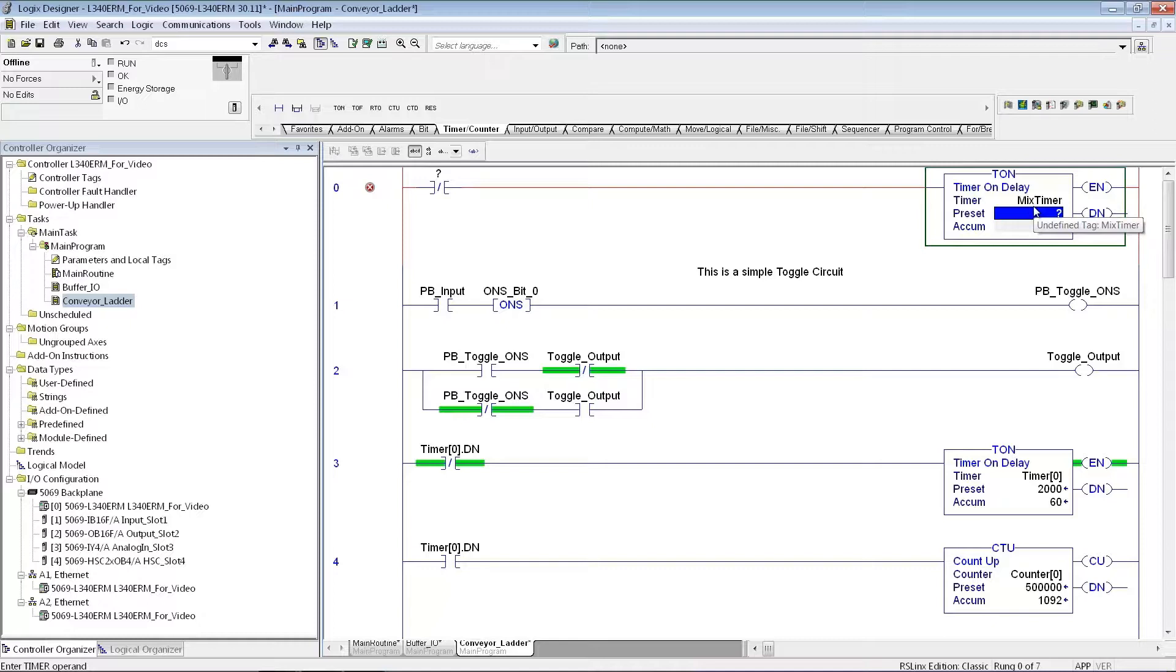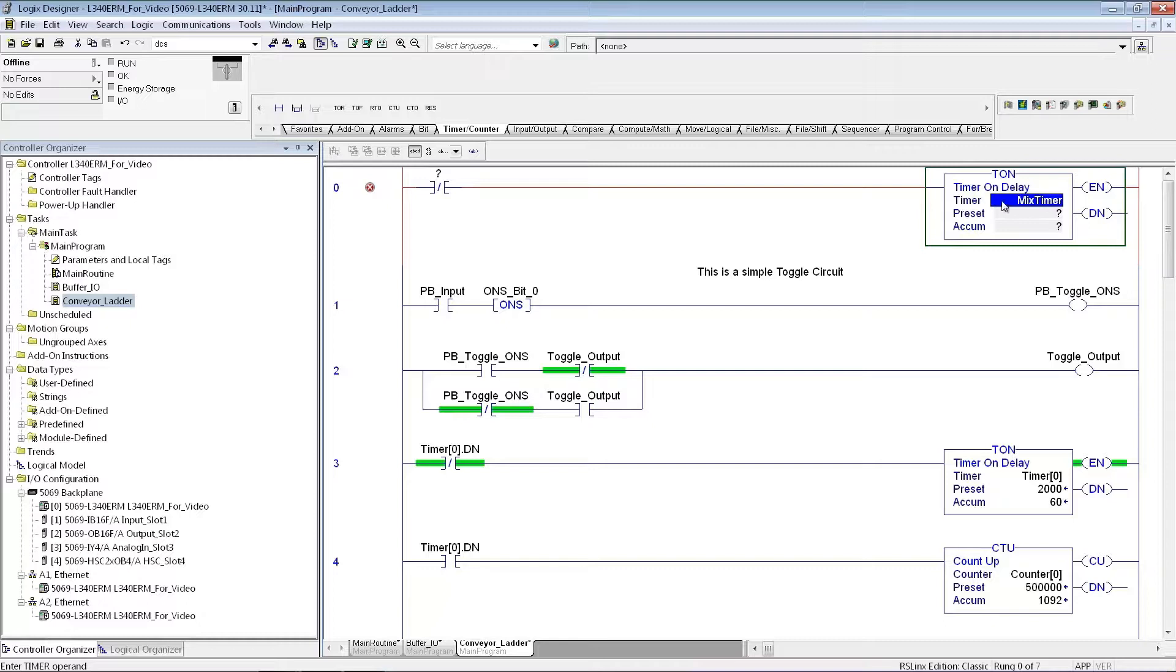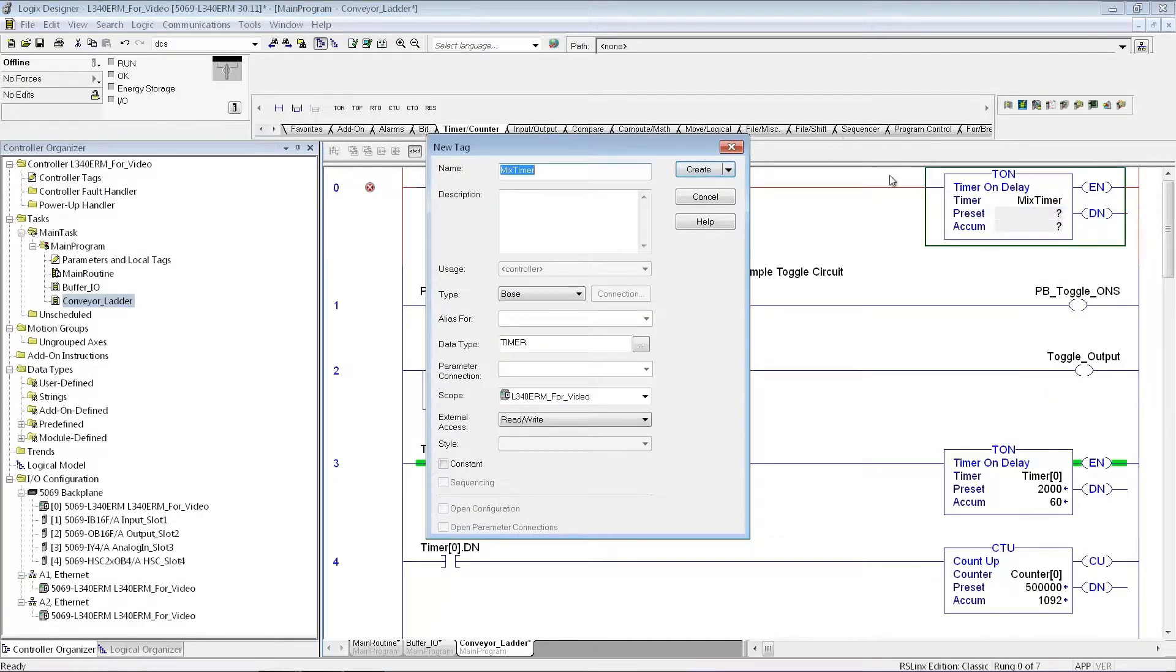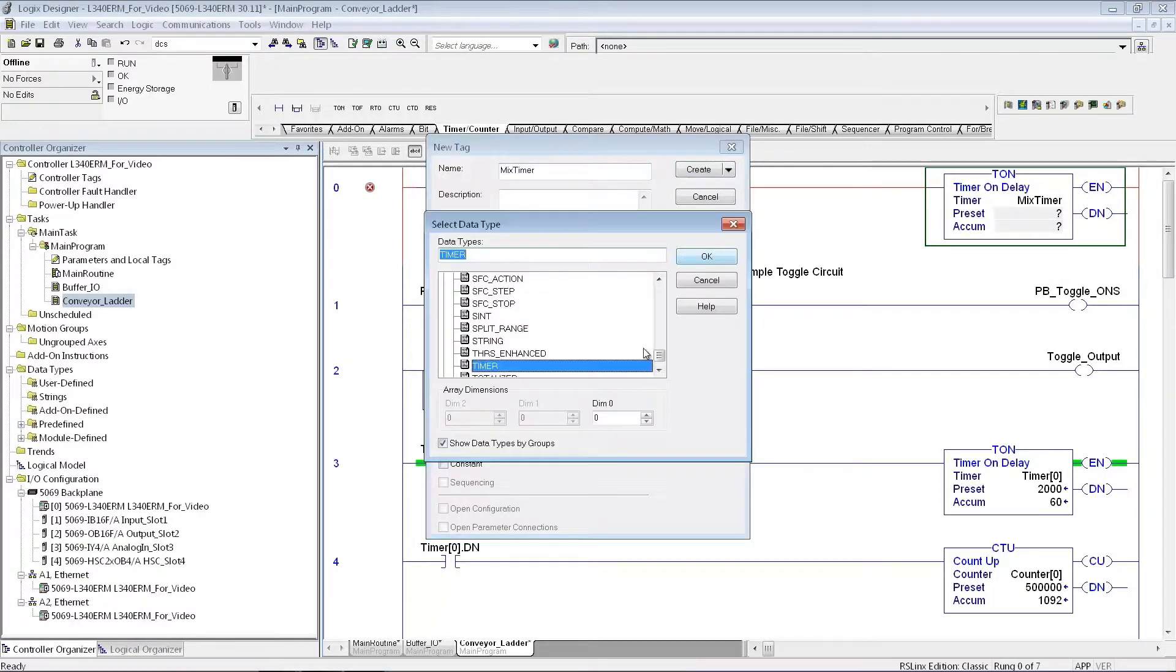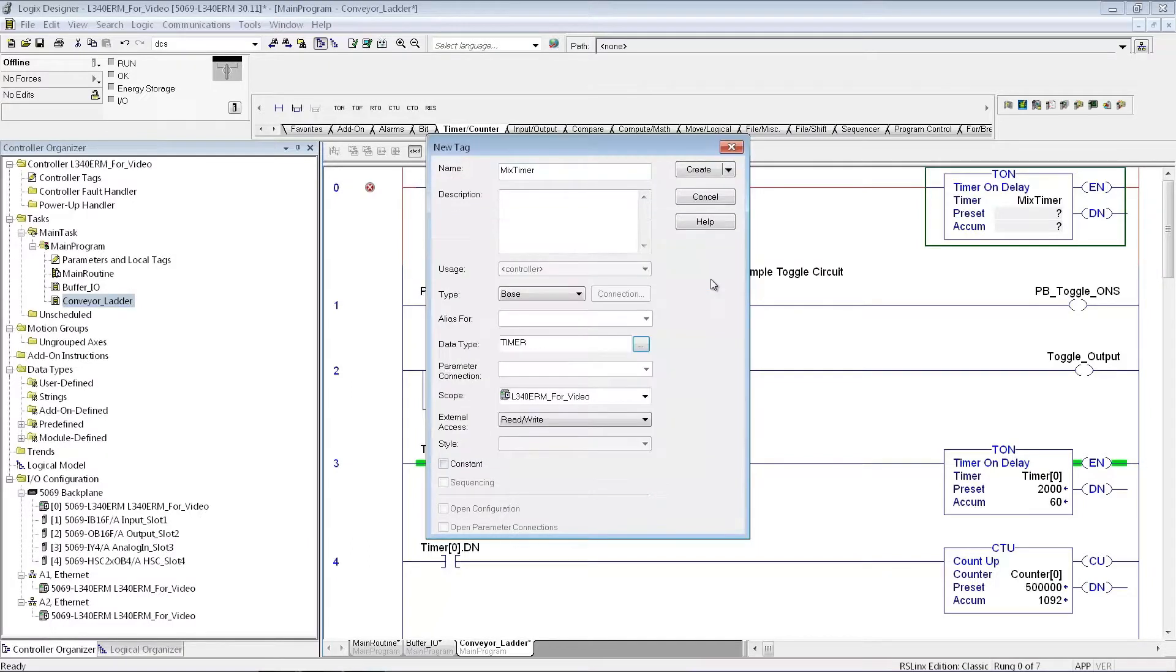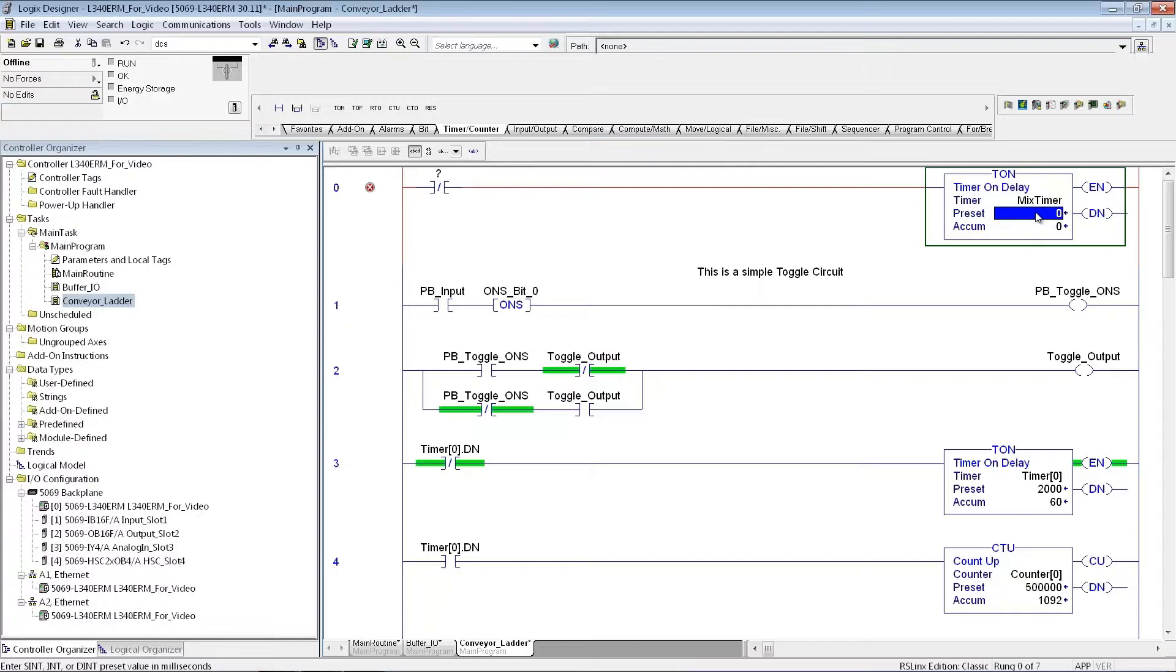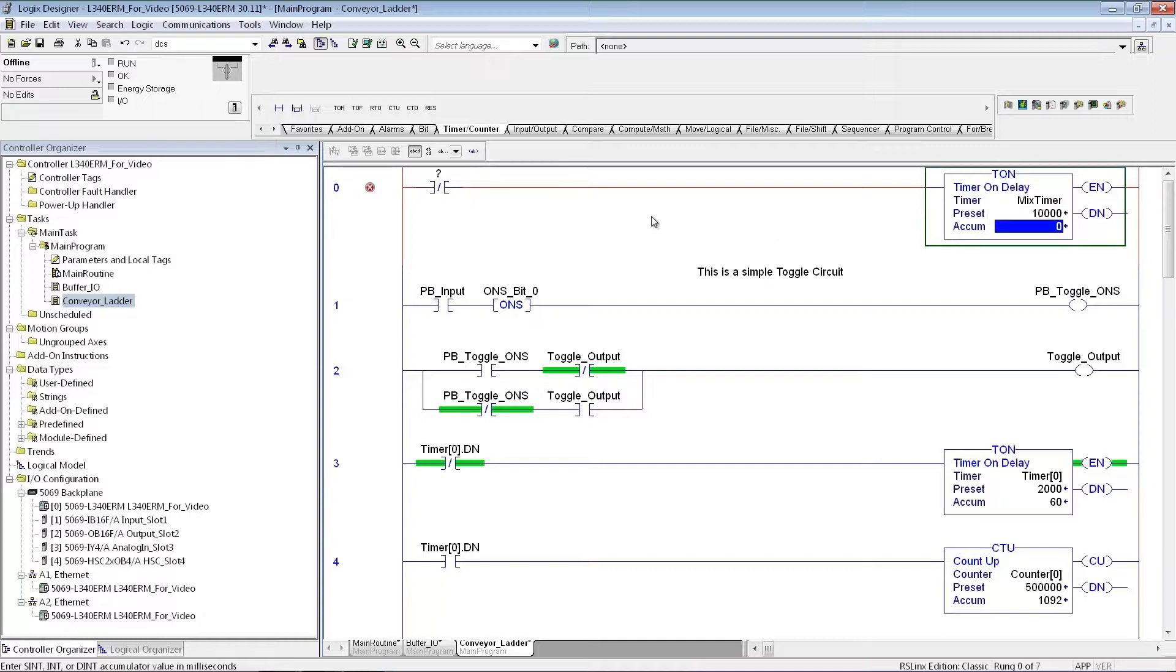Give it a preset of whatever. All of the timers in the control objects are based on milliseconds. So if I put in a value of 10,000, that's 10,000 milliseconds. So I set up my timer, I'm calling it Mixed Timer. I need to create that, so I right click on that. Mixed Timer, it's going to be of type Timer. I can make an array of timers if I wanted to. In this case, I'm just going to make one.